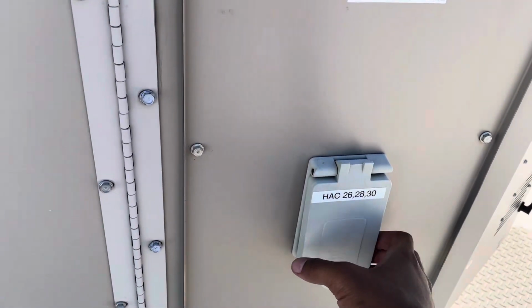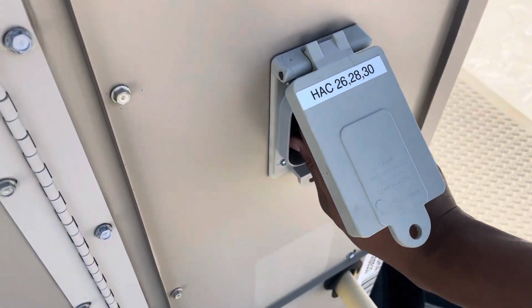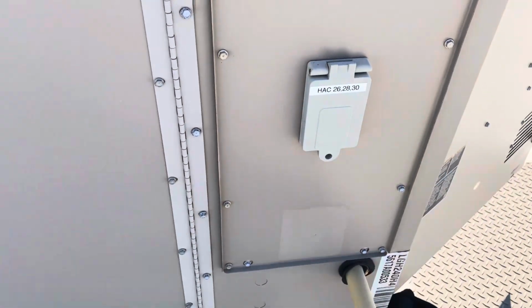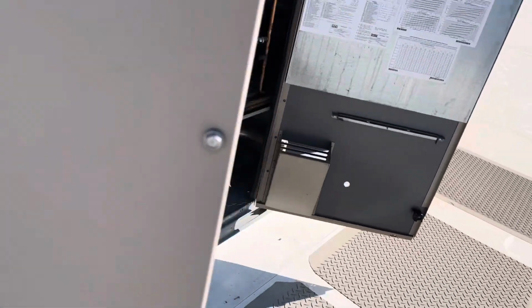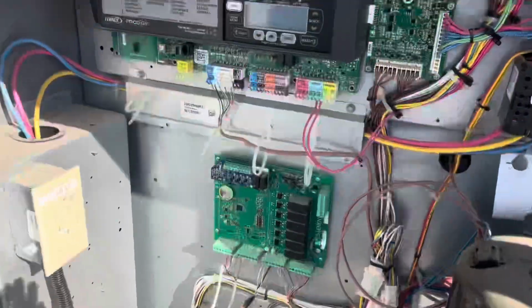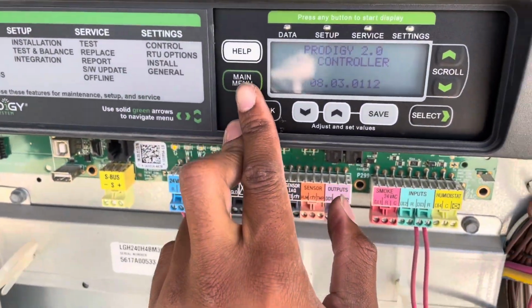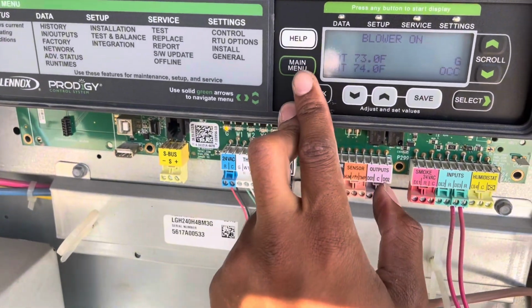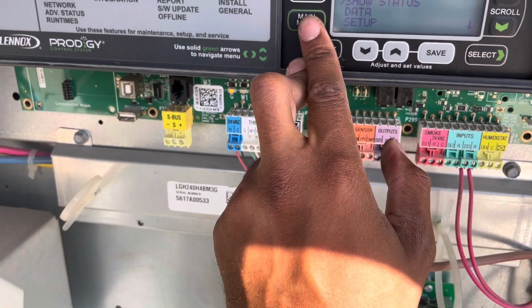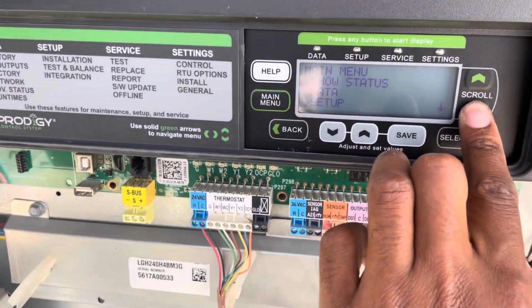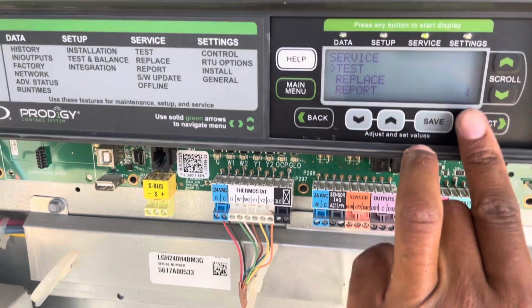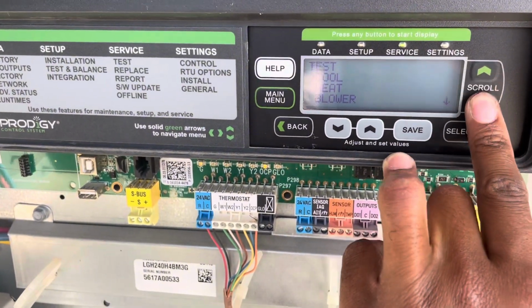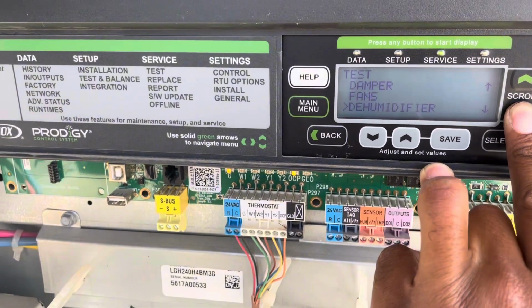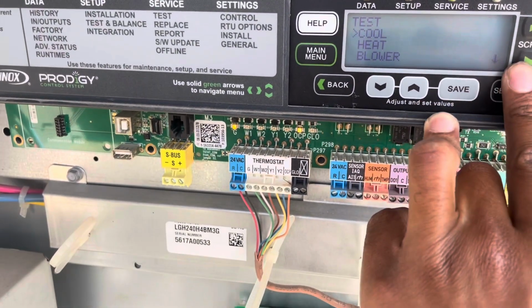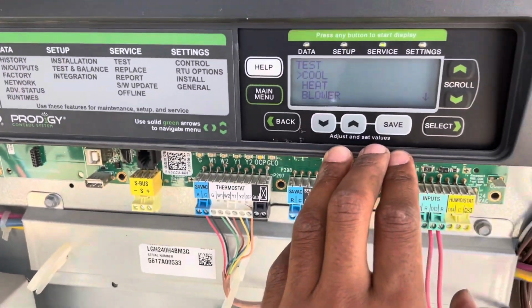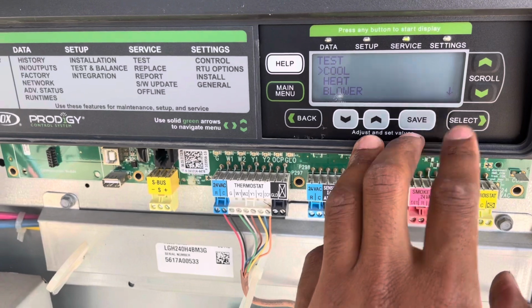And from the control board, we will test heat, just so that you can see the sequence of operations. On these new controllers, anytime you want to put the unit in test mode, you go to main menu, scroll down to service, select test. You can test cool, heat, blower, damper, fans, everything. Pretty cool. I actually really like this controller just because it's so simple to test what you need to test.